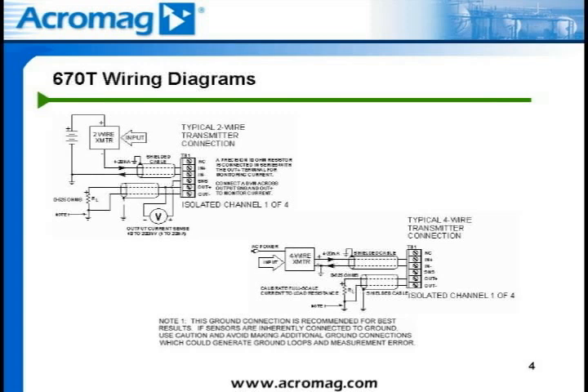The next DC current monitoring application is typical of a four-wire device. The loop is powered from the field device and no external power supply is required in the loop. For this application, the connections are simply field device positive to the IN+ terminal and field device negative to the IN- terminal. The output connections are the same as shown in the two-wire transmitter connection. Be sure the input power is sufficient to provide for the total burden induced by the 670T module and the output load at full-scale current.